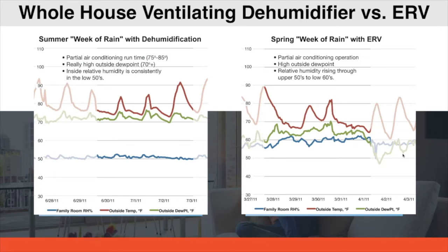So what we did after we did some data logging and ran that ERV, we took out the ERV and put in a ventilating dehumidifier, used it for ventilation to meet the ventilation code, set the RH to 50%. And again, the green line there is the dew point. We really don't care what the dew points are outside. We're going to focus on controlling that relative humidity inside to a dedicated RH set point.